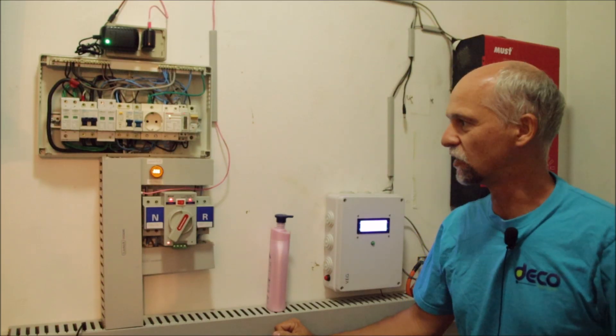In the case of a faulty panel with a leakage between the power line and the frame - the frames are grounded of course - if you have installed a type B RCD it should trip, but also internally the inverter should detect such a leakage and present a fault and shut down. So always keep your PV DC side isolated if you can. I will now show you on my all-in-one inverter how a measurement would look like and how you could find out if your inverter is transformer-based or transformerless.